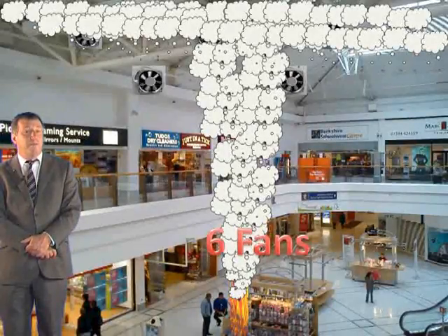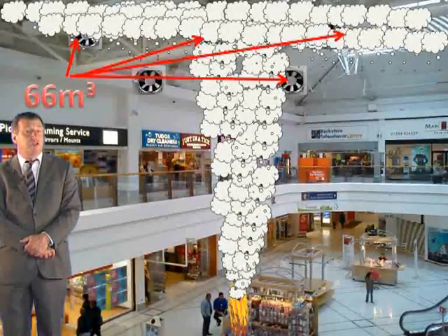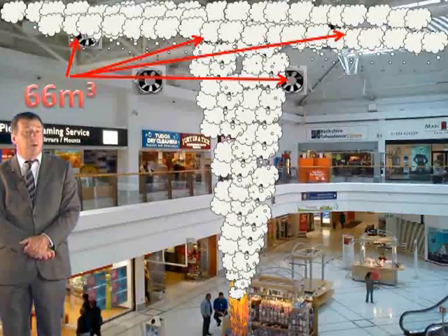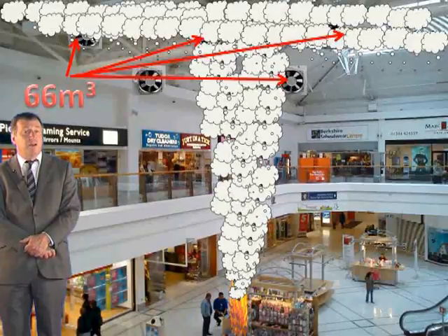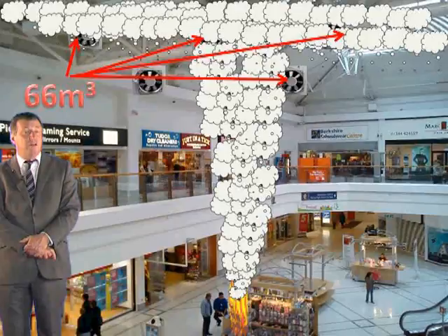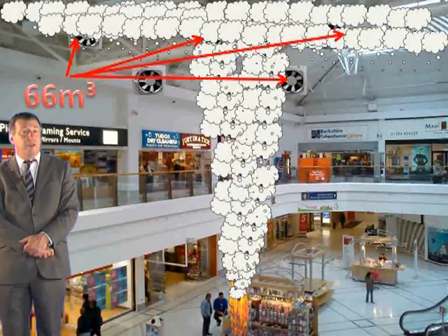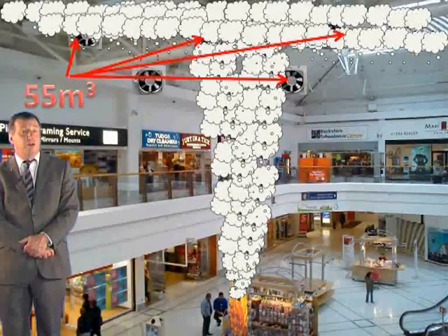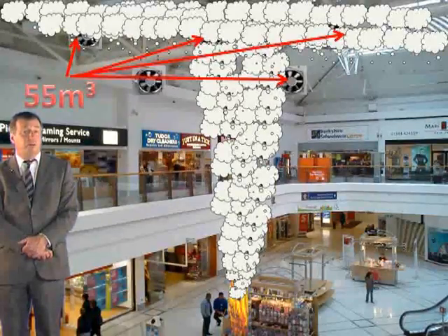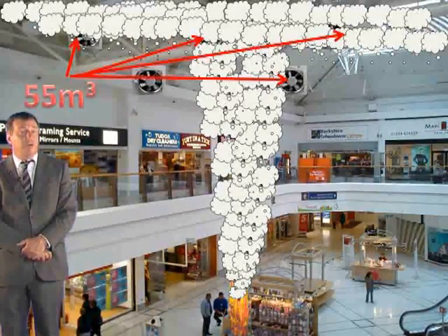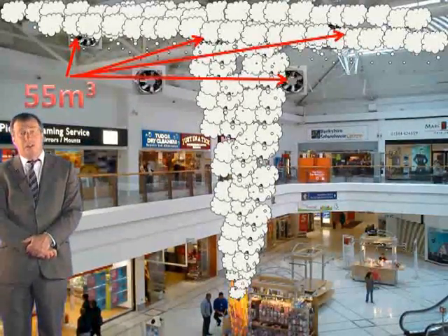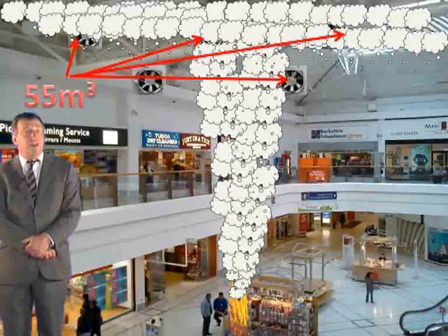If none fail, then we shall be extracting 66 cubic meters per second, which is considerably more than the figure we need of 50.35 cubic meters per second. But that's okay. It simply means that the smoke layer will not descend as far as our design height. If we were confident that no fan would be lost to fire, then we would be satisfied with 5 fans, which would have a total capacity of 55 cubic meters per second, and again this is slightly more than is required. That's step 7 covered, so now we can move on to step 8, the stagnation check.